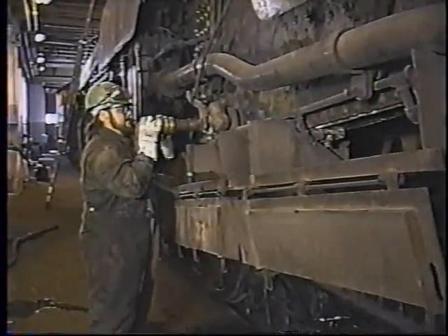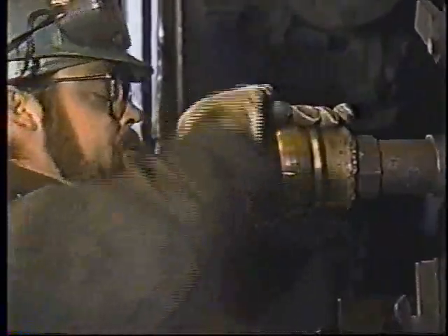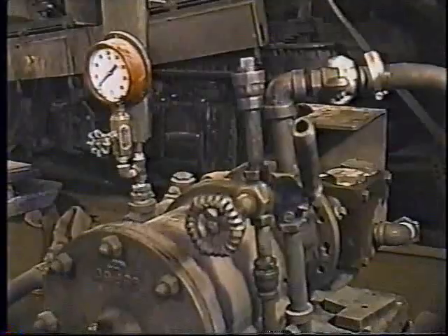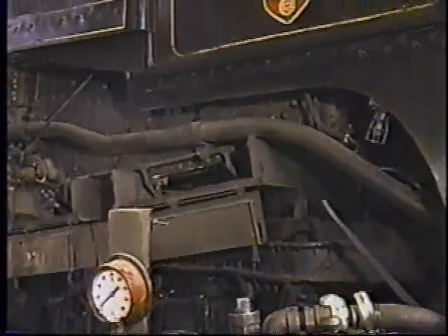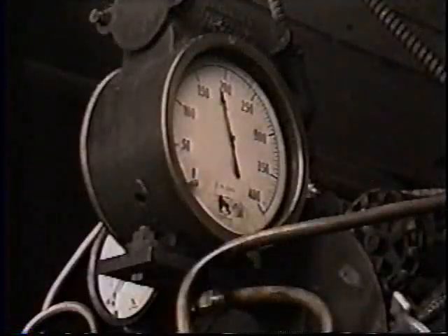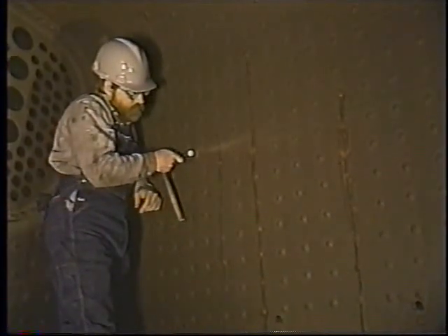Preparatory to the test, the boiler is completely filled with water. The relief valves are either gagged or removed and the openings are capped off. The test is performed by increasing the pressure on the water-filled boiler until it reaches a pressure that is at least 25 percent higher than the normal working steam pressure of the boiler. This will allow any leaks or defects to surface without the danger of a high-pressure steam explosion. Once the boiler is at pressure, examine the firebox for leaks, bulges, or corrugations.